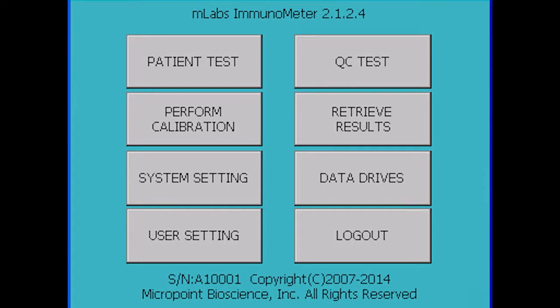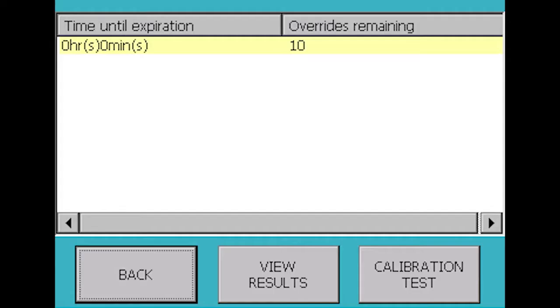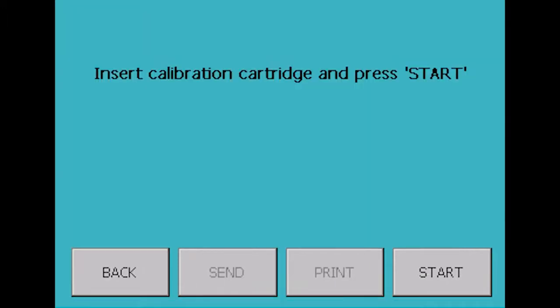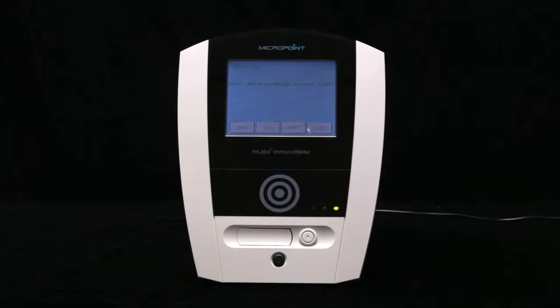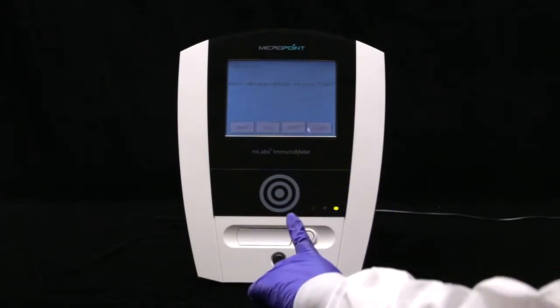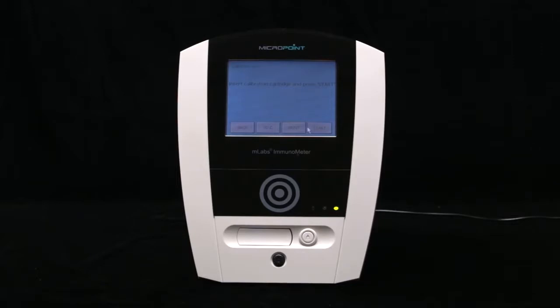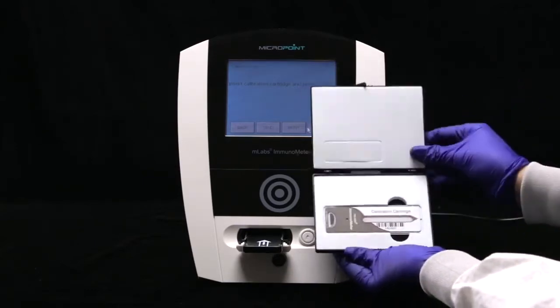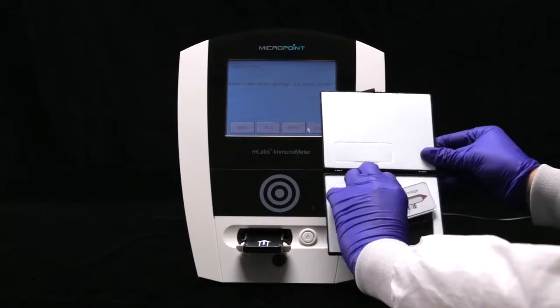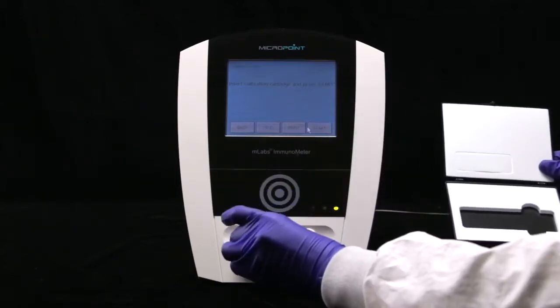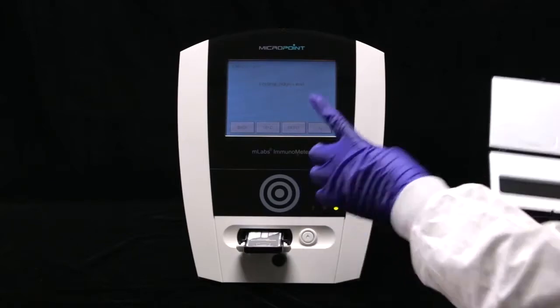To perform a calibration, touch Perform Calibration on the main menu. You will find time until expiration and overrides remaining on the screen. Tap Calibration Test to perform a calibration. Press the cartridge holder eject button to eject the cartridge holder. Place the provided calibration cartridge with the inlet well pointing out and the barcode on the right. Touch Start to perform calibration.